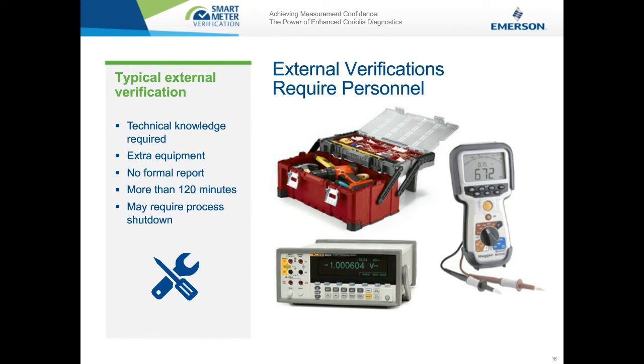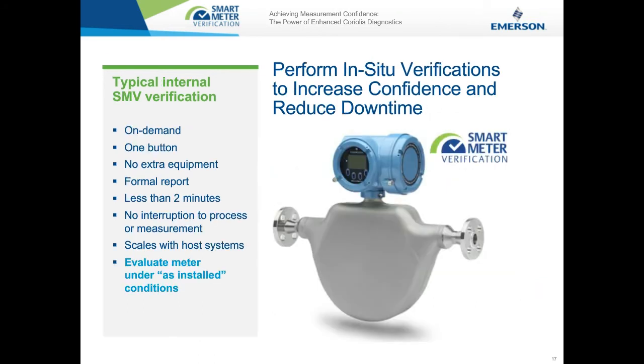Which is exactly why we're seeing these in situ or inline verifications becoming more and more popular in the process industries today. In situ verifications don't stop at the laboratory door. They evaluate meters under as-installed conditions, which can be very powerful. The ability to have this sort of on-demand and automated verification that doesn't interrupt the measurement is quickly becoming the new standard for Coriolis diagnostics.